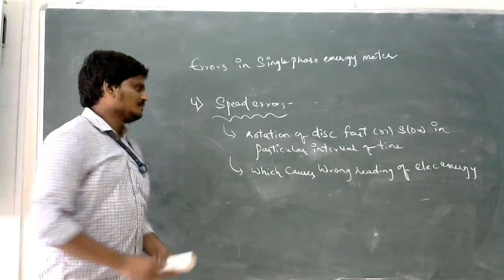using a braking magnet. The speed error can be compensated by using a braking magnet at the edge of an aluminum disc. And this braking magnet is adjustable, so that by using this braking magnet, the speed of the disc can be adjusted to a desired value. By using the position of a braking magnet, the speed can be adjusted to a desired value.